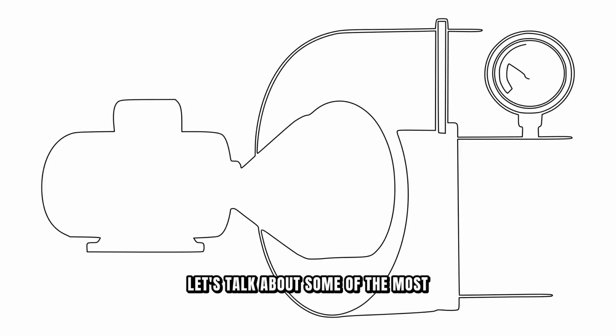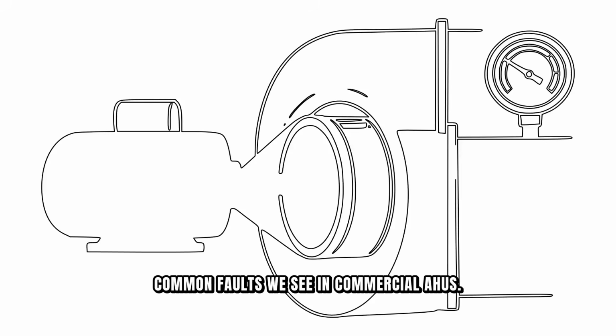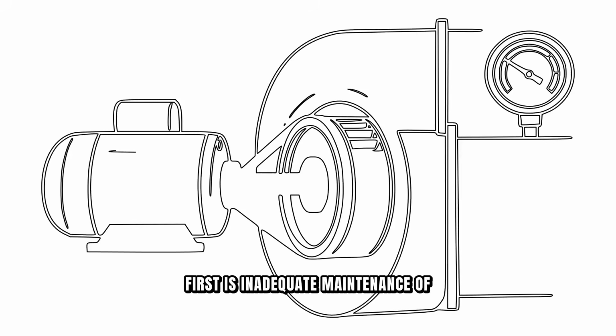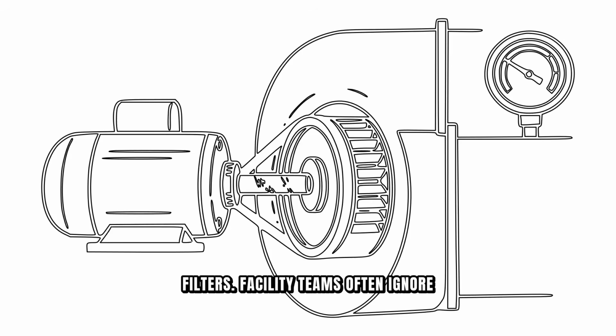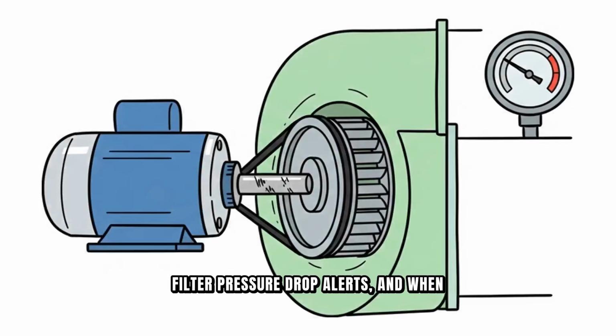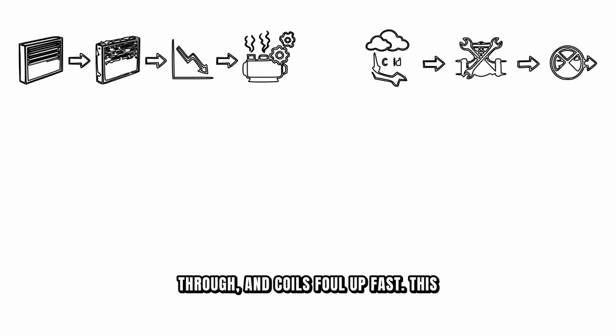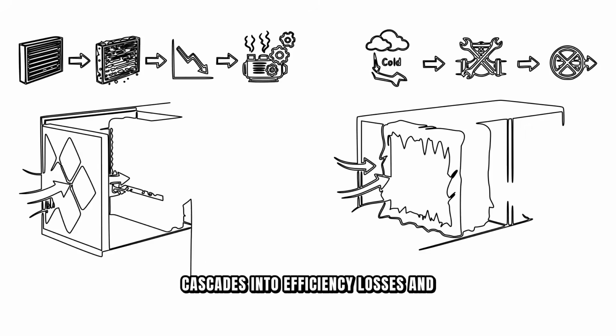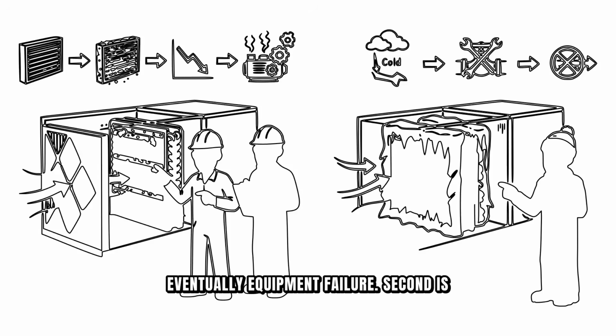Let's talk about some of the most common faults we see in commercial AHUs. First is inadequate maintenance of filters. Facility teams often ignore filter pressure drop alerts, and when filters finally plug completely, air bypasses them around the sides, dirty air gets through, and coils foul up fast. This cascades into efficiency losses and eventually equipment failure.